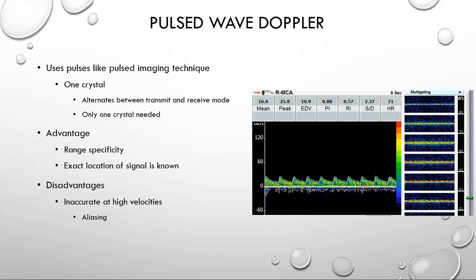Pulse wave Doppler is the Doppler used to obtain our spectral display at the bottom of a duplex image. It uses pulses like pulsed imaging technique, typically uses one crystal, and alternates between transmit and receive mode. The advantage is good range specificity — we know the depth our Doppler signal is coming from. The disadvantage is we can get aliasing with high-velocity blood flow.